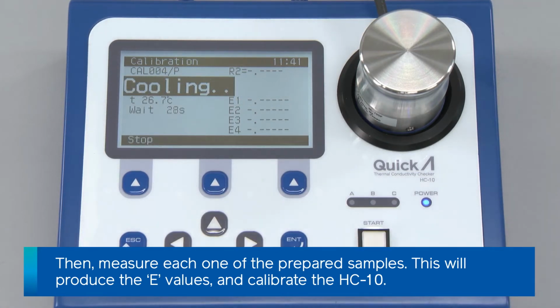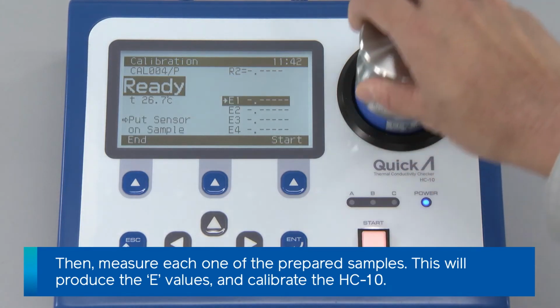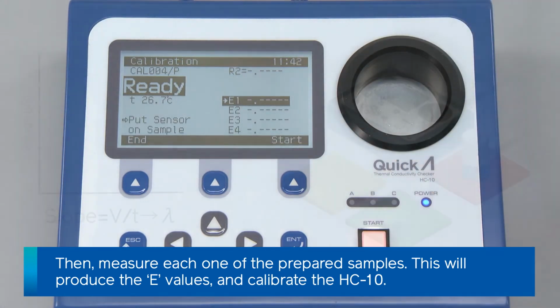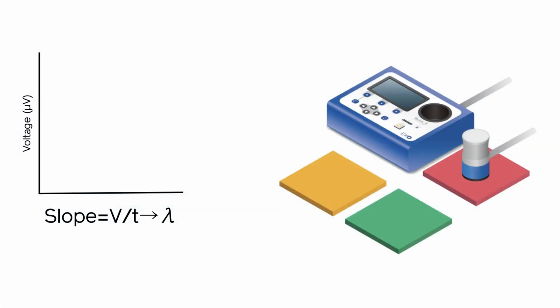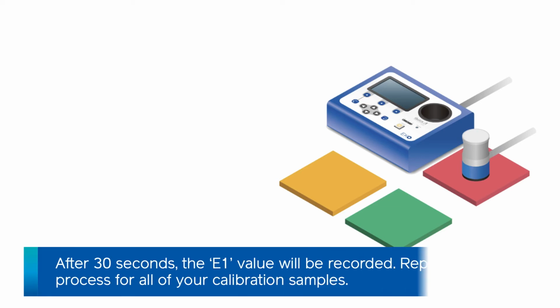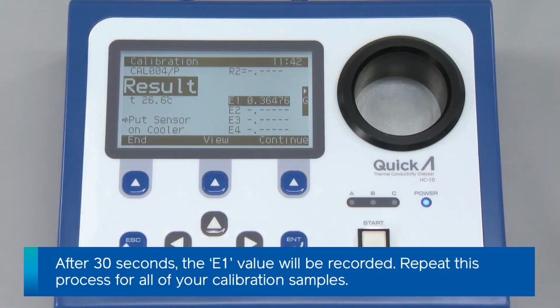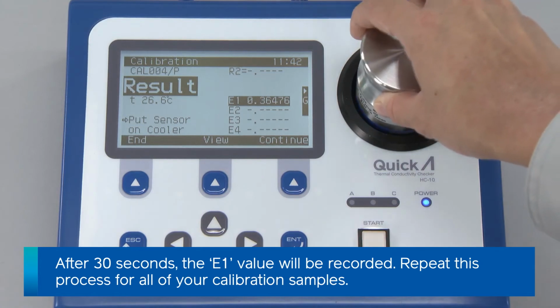Allow the sensor head to cool for 30 seconds. This will temper the sensor head for measurement. When the status changes to ready, place the sensor head on the first sample to measure E1, which relates to lambda 1, and press the Start button again. After 30 seconds, you'll see the E1 value, meaning you successfully measured the first calibration sample. Repeat this process for the rest of the samples to finish the calibration.